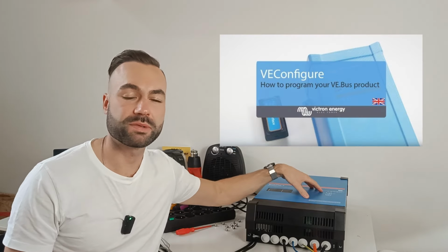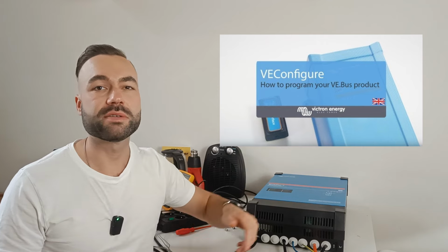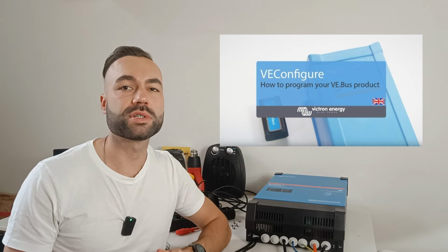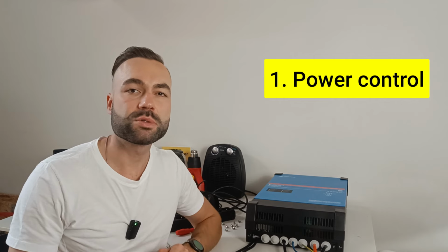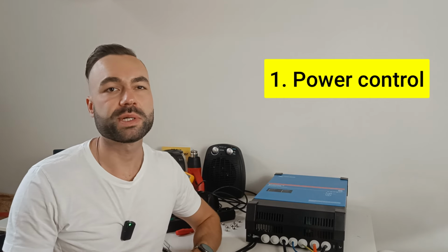As with life in general, the good things come from within. In this case, it's the software. Here are the key features that make the MultiPlus stand out. Power control helps to avoid overloading your generator or the grid. You set a maximum input current, and the MultiPlus will ensure your system stays within that limit. If you have extra input power, it diverts it to charging the batteries.